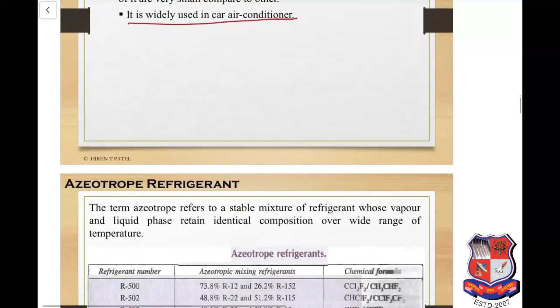Now what is azeotropic refrigerant? The term azeotrope refers to a stable mixture of refrigerants whose vapor and liquid phases retain identical composition over a wide range of temperature. So in the table, some of the azeotropic refrigerants are indicated, that is R500, R502, R503 and R504.